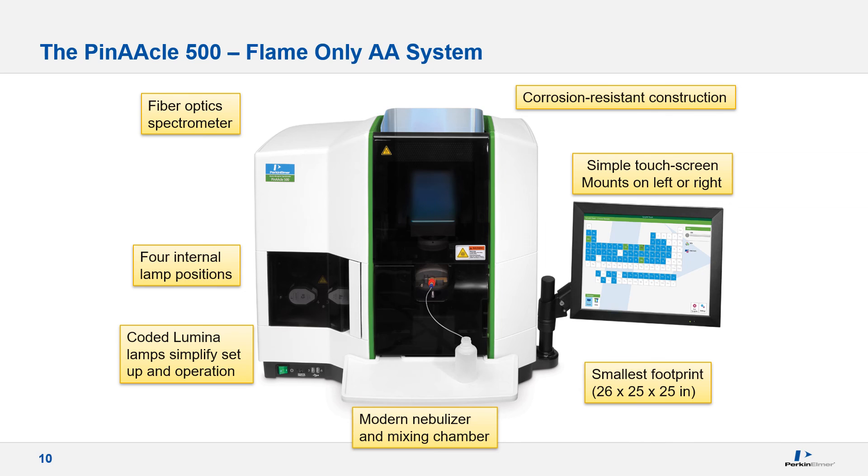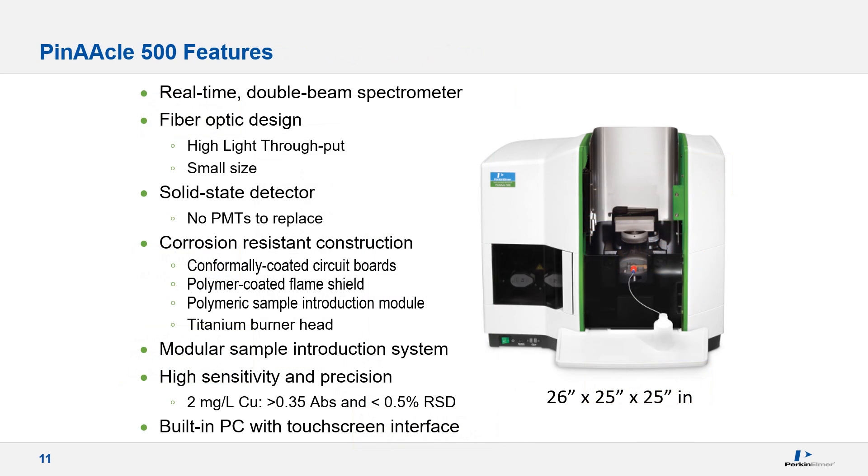The Pinnacle 500 features fiber optic technology, Coded Lumina lamps available in four positions, a more modern nebulizer and mixing chamber design, corrosion-resistant construction, a touch screen that can mount on either side, and the smallest footprint available. Real-time double beaming improves precision over traditionally designed systems by using a sample and reference beam to account for short-term lamp intensity fluctuation. I have already discussed the benefits of fiber optic technology as it relates to improved light throughput.